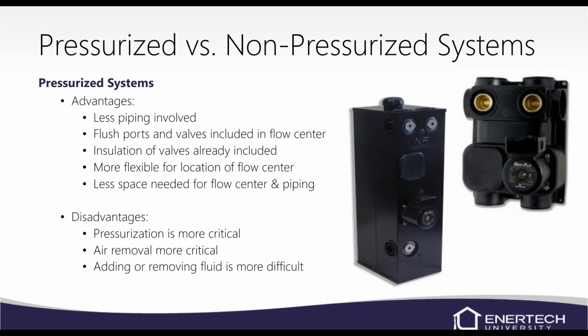So some of the advantages of the pressurized flow center is on the right side in that picture, the smaller of the two. There's less piping involved with the pressurized system. The flush ports and the valves are included on the flow center, although the new NP series, this black cabinet, has the 3-way valves on it as well. But if you happen to go with maybe a QT flow center, it does not have those. But the new NP series with this composite or black shell, they do have 3-way valves, so you can actually isolate the flow center from the loop field, and you can actually flush right at the flow center there.